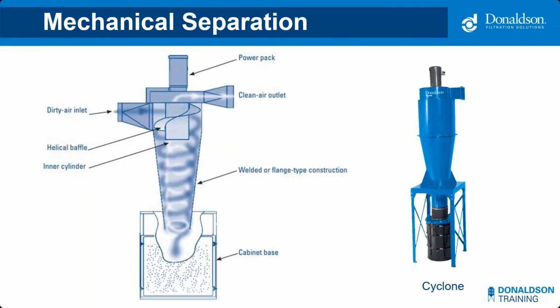Mechanical separation, you might also hear these referred to as cyclone collectors. These use centrifugal force to separate the dust from an airstream. You can see in the diagram on the left that the dirty air comes in the side and is directed through a helix baffle to create a cyclonic spin inside of the collector. The dust particles travel with inertia and impact the inner wall of the cyclone. Consequently, they lose their velocity and will drop out to the cabinet base bin at the bottom. The clean air is not as affected by inertia and won't impact the walls and drop out. So the clean air will rise up through the middle of that helix baffle and exit through the clean air outlet at the top of the collector.